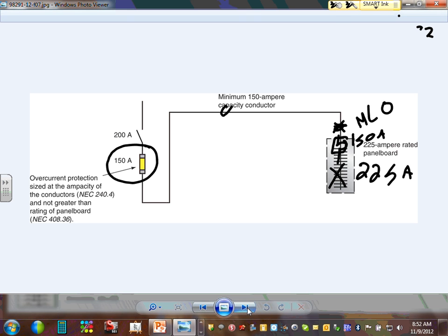So this is called main lugs only. If you put it inside, it becomes main circuit breaker. Do you guys understand? You use them in Revit, right? Main lugs only, main circuit breaker. Main circuit breaker has a main in it. Main lugs only does not have a main in it. Any comments, any questions? Which one is the cheaper? No main in it. Which one is better in terms of design? No main in it too.